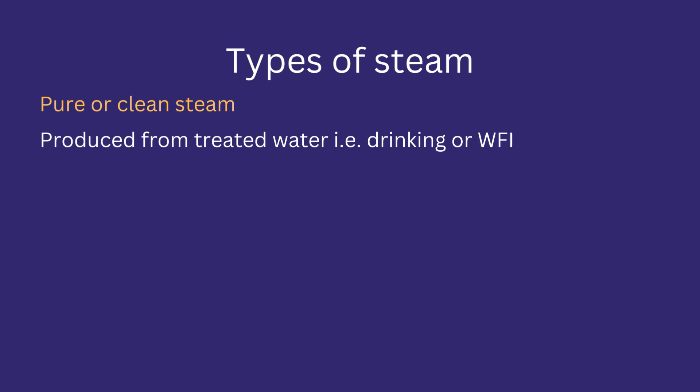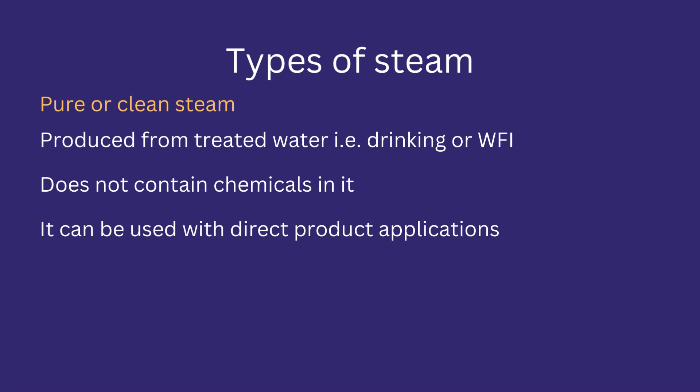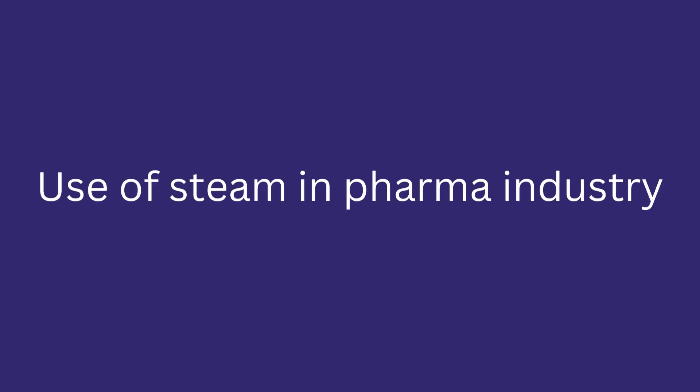Pure or clean steam is produced from treated water that meets standards equal to USP drinking water or water for injection (WFI). Pure or clean steam does not contain chemicals because the feed water does not contain them. This type of steam can be used for critical applications where the steam comes in direct contact with the product. As mentioned earlier, pure or clean steam is produced using a steam generator.